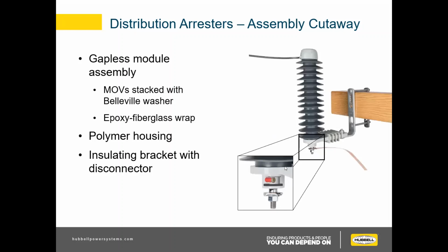Now a really proud product that we have here is our insulating bracket. We pride ourselves on our capacitive graded disconnect rather than a resistive graded one, because it gives us several advantages. One of those is TOV handling capability, as well as more sensitive disconnection. That increases the reliability of your system, because, as I'll go over more in a minute, this disconnector will operate down to 1 amp, where the standard only requires 20 amps to disconnect it and take the arrestor out of system.